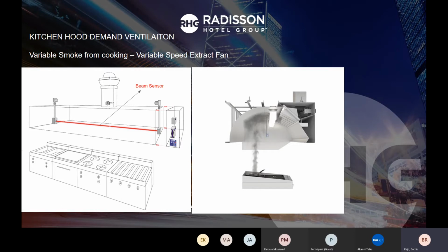So in this case, I'm saving on two aspects. The first one is the current, or the amps, consumed by the motor. When ramping down, in case there is not much cooking, it is less. So I'm saving on the motor energy consumption. Also, when the fan is extracting the air, it's throwing out the air conditioning from the kitchen. So instead of always throwing out a constant amount of cold air, it is reduced when there is not much heavy cooking on the cooking range. This is one of the approaches of sustainability. We have no more constant. We always have a variable input, depending on the smoke concentration, and a variable output on the fan running and extracting the air.